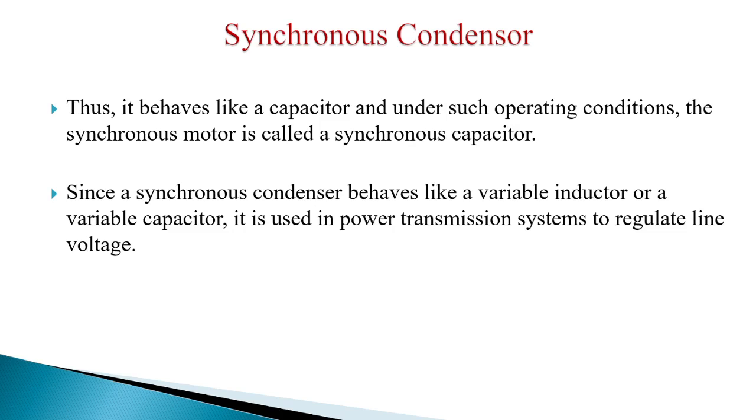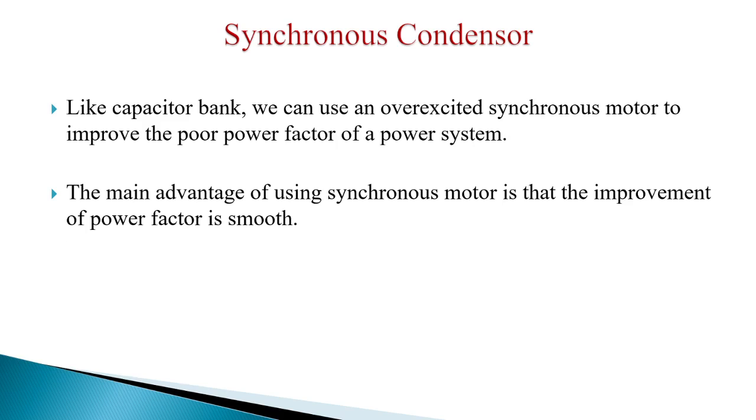Since a synchronous condenser will behave like a variable inductor or a variable capacitor, it is used in power transmission systems to regulate line voltage. Like a capacitor bank, we can use an overexcited synchronous motor to improve the poor power factor of a system.